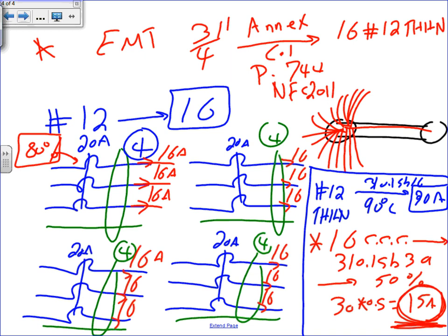Okay. I did all this, guys, to prove to you that the grouping we have done makes sense. Unlike the book that we had, where he started grouping and all this stuff, and you wonder, does it really make sense to group the air handling unit with this and that? It might not make sense. Here's where it makes sense to group them. Anything 20 amp, number 14 to 12, group. Anything higher than that, don't.